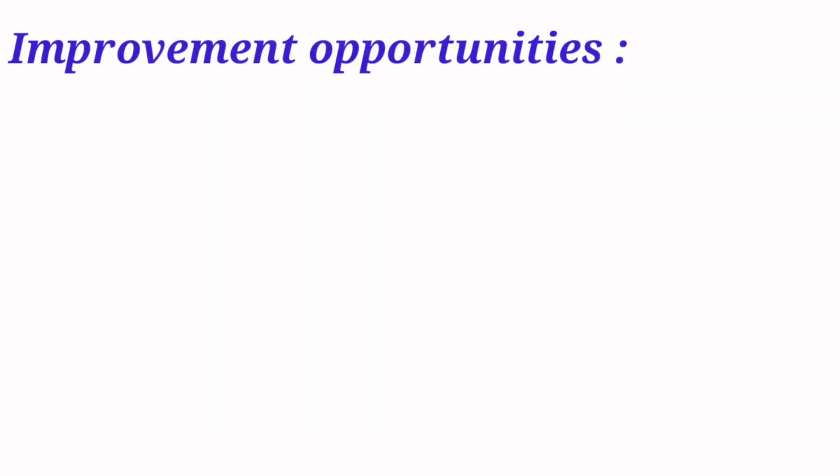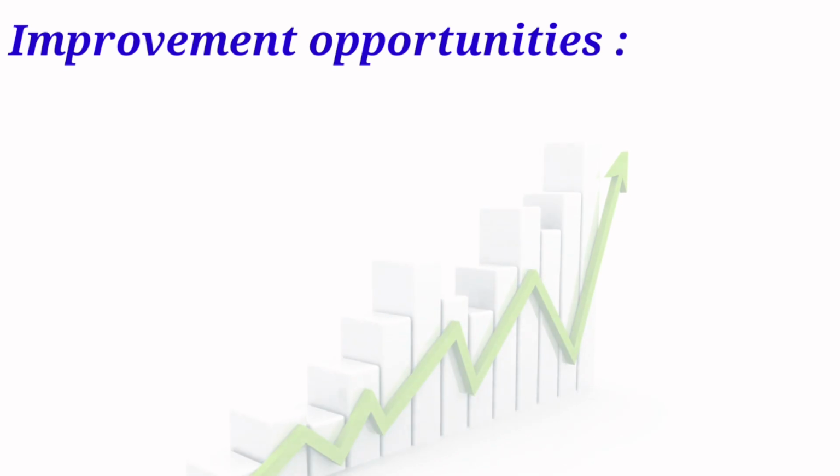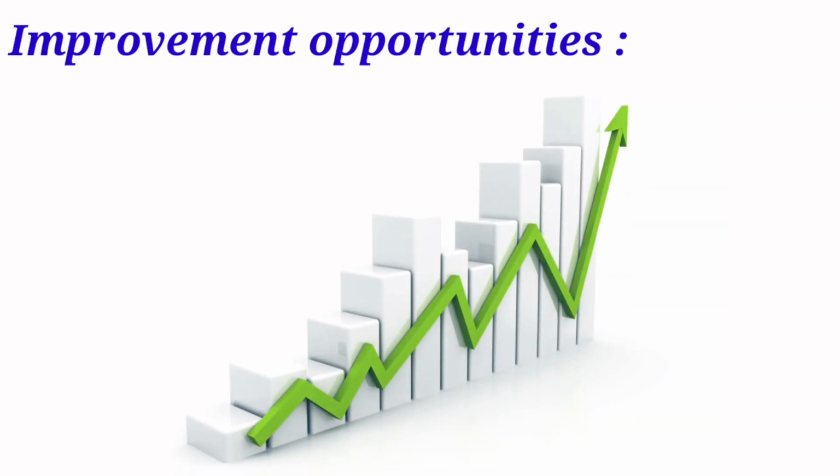FCU improvement opportunities. The major areas for improvement for FCU systems are review and optimization of zone temperature control for FCUs, recommissioning and maintenance of chilled water and hot water flow balancing and valve operation, upgrade of controls for boilers, chillers and associated pumps, upgrade of chiller plant.